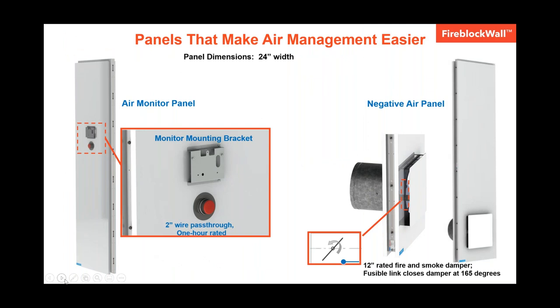We make air management easy with two different 24-inch wide rated panels that work together. The first is the negative air panel, which has a 12-inch duct that can be used with a HEPA machine to discharge air. The air diffuser only discharges air upward and sideways, limiting disturbance of dangerous dust on the floor. It also features a fusible link that automatically closes the damper when the temperature exceeds 165 degrees. The second is the air monitor panel, which features a universal mounting bracket that accepts all common manometers, and also has a two-inch rated passthrough for wiring.